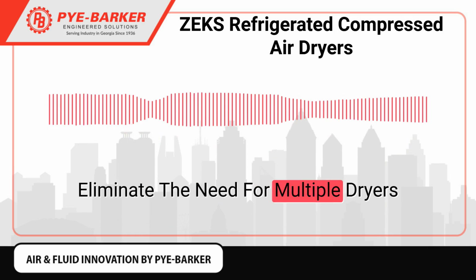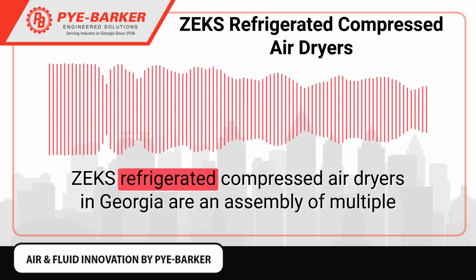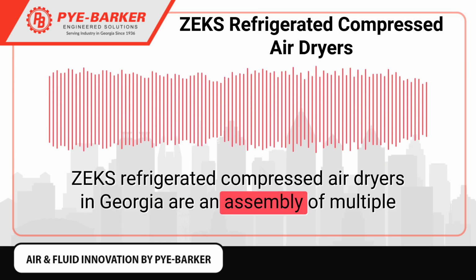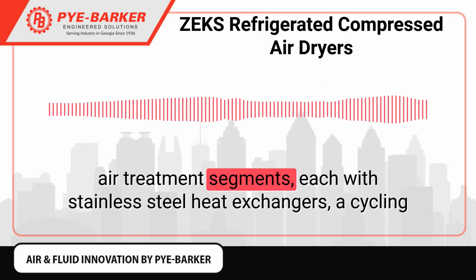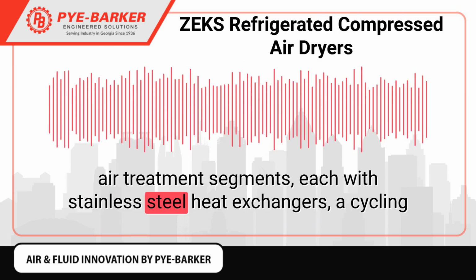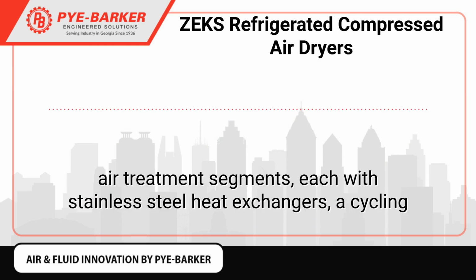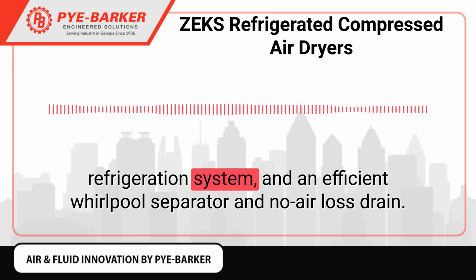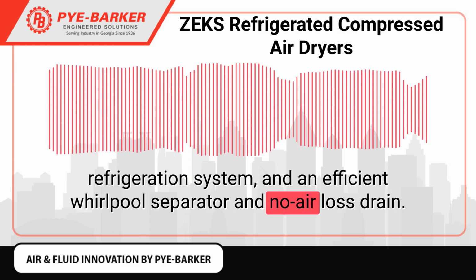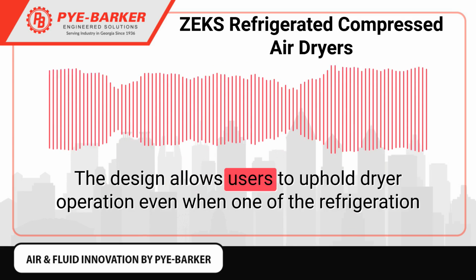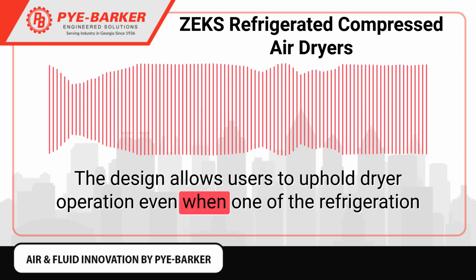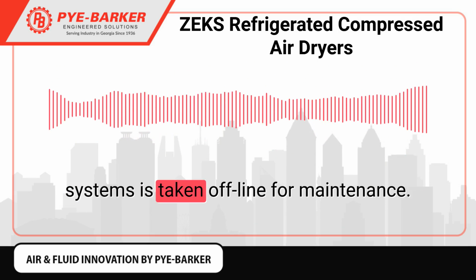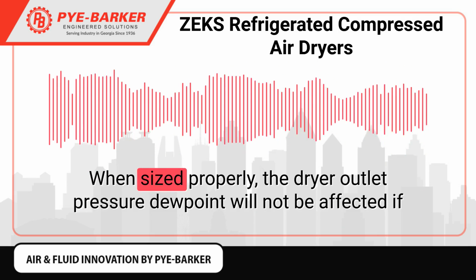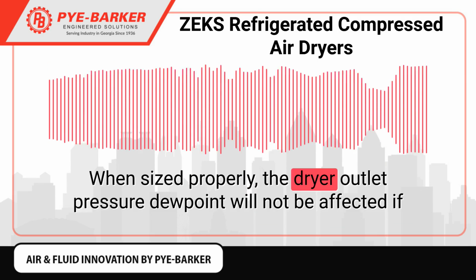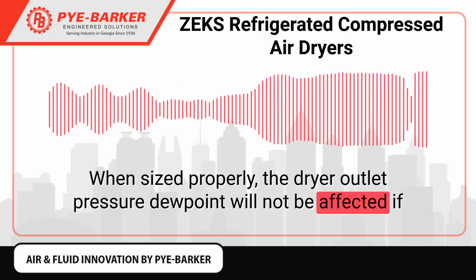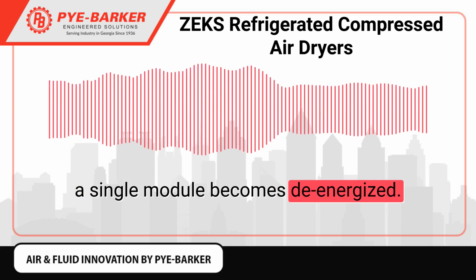Eliminate the need for multiple dryers. ZEKS Refrigerated Compressed Air Dryers in Georgia are an assembly of multiple air treatment segments, each with stainless steel heat exchangers, a cycling refrigeration system, and an efficient whirlpool separator and no air loss drain. The design allows users to uphold dryer operation even when one of the refrigeration systems is taken offline for maintenance. When sized properly, the dryer outlet pressure dew point will not be affected if a single module becomes de-energized.